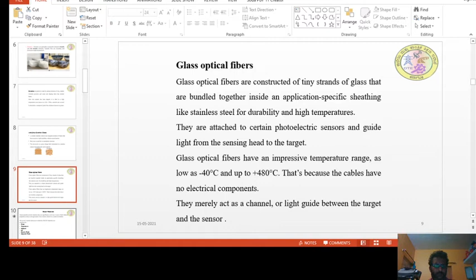Coming to the glass optical fibers. Glass optical fibers are constructed of tiny strands of glass that are bundled together inside an application-specific sheathing like stainless steel for durability and high temperature. So here the glass optical fibers are formed by small threads joined or twisted together and covered by some form of sheathing. Usually it is stainless steel. They are attached to photoelectric sensors and guide the light from the sensor to the target. The function of this is that it will receive the light from the receiving end and send it to the target. The glass optical fibers have an impressive temperature range, as low as minus 40 degrees centigrade to plus 480 degrees centigrade. This is possible because the cable has no electrical components. They merely act as channels, light guides between the target and the sensors.